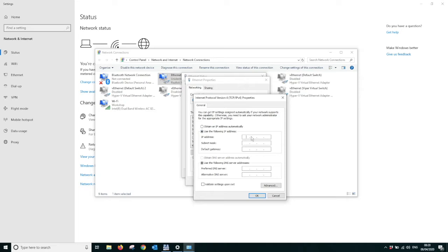Now the controller comes from factory with a default IP address of 192.168.1.99, so we have to be anything other than 99 between the range of 1 and 255. So 255 is excluded, but we can go to 254 or 1, or anything other than 99, shall I say. So I'm going to choose 100, and the subnet mask is 255.255.255.0. We don't need to put a default gateway in for this exercise, and leave the DNS server just ticked as is.